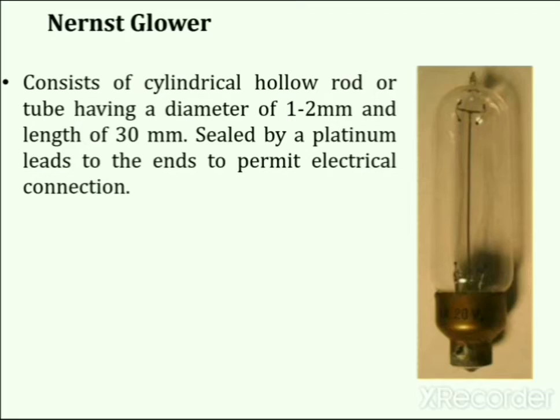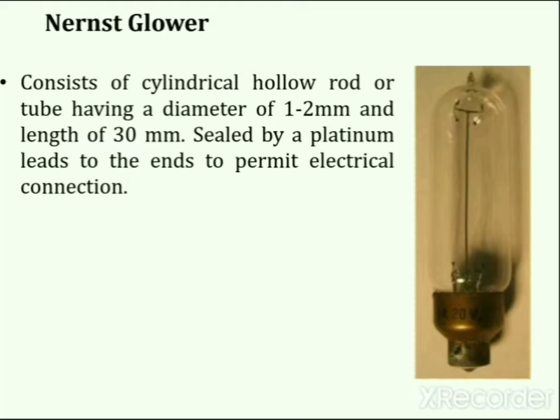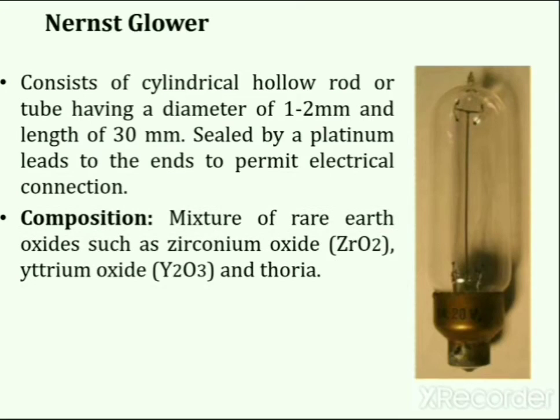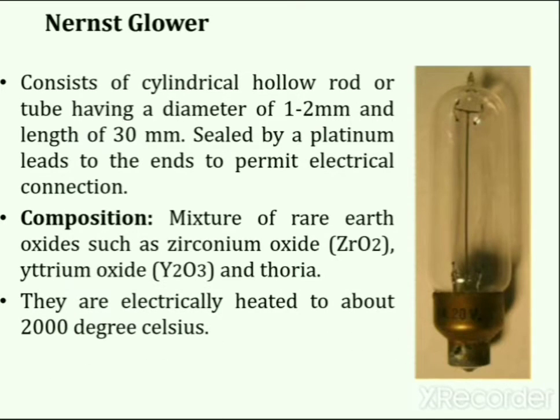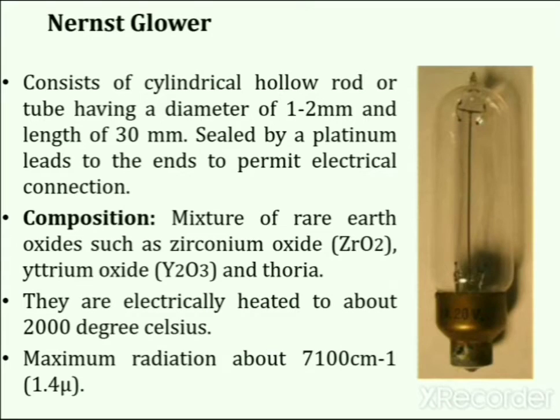The Nernst Glower consists of a cylindrical hollow rod or tube having a diameter of 1 to 2 mm and a length of 30 mm, sealed by platinum leads at its ends to permit electrical connection. It is composed of a mixture of rare earth oxides such as zirconium oxide, yttrium oxide, and thorium oxide. When heated to about 2000°C electrically, it generates IR radiation, providing maximum radiation at about 7100 cm⁻¹. Its lifetime depends on the operating temperature and the care taken in handling.